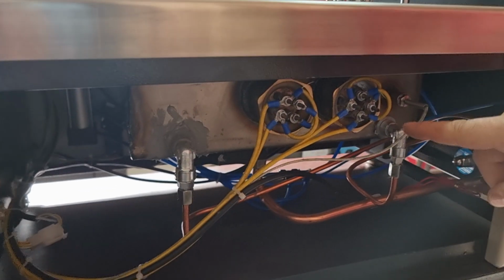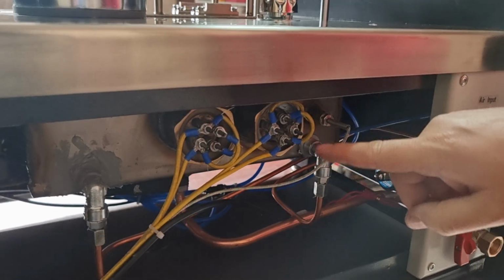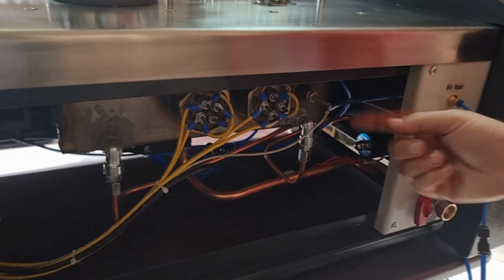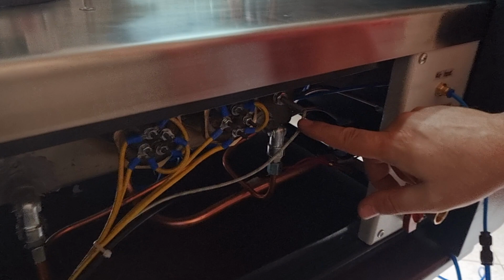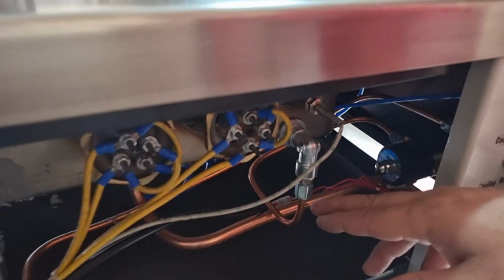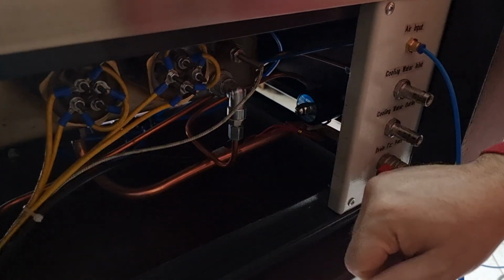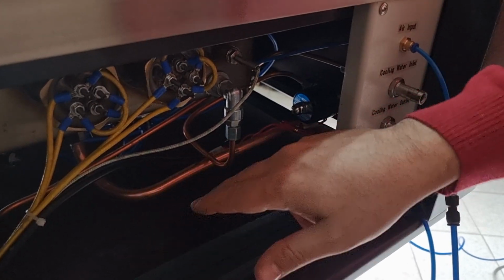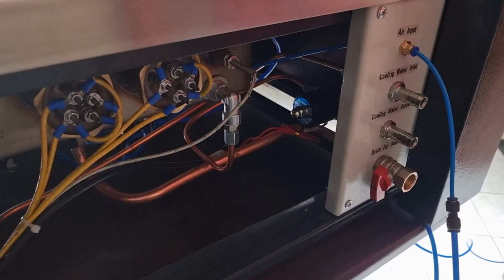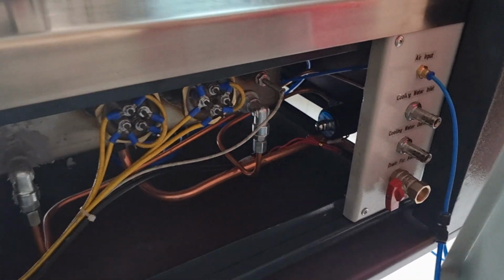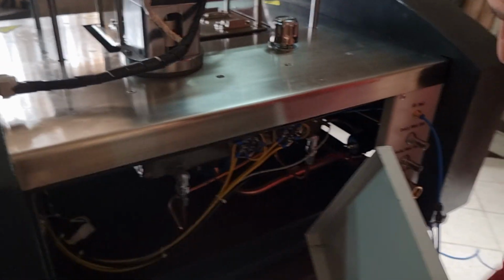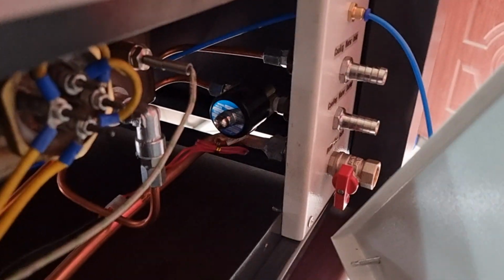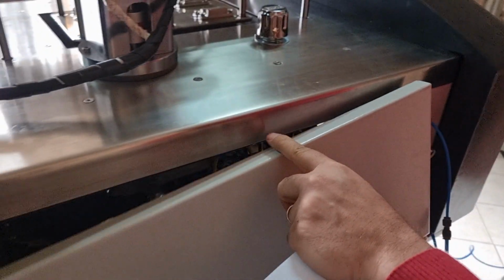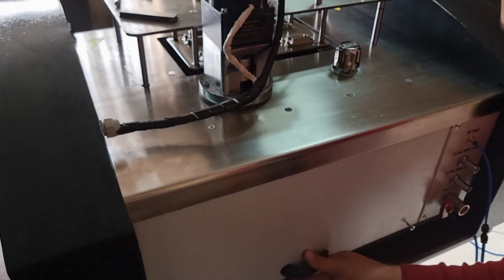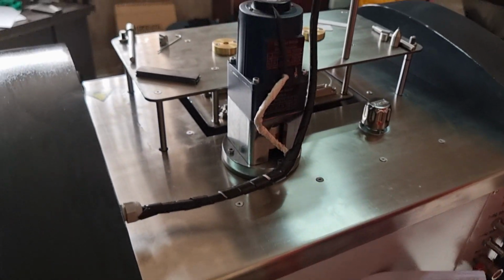In the back panel, you have easy access to heating elements. You have two flange type heating elements. You can easily replace it here. You have a sensor for reading the temperature of the oil bath. You have the hydraulic plumbing for the cooling water, and also you have an automatic valve, a solenoid valve, for controlling the cooling water inlet here.